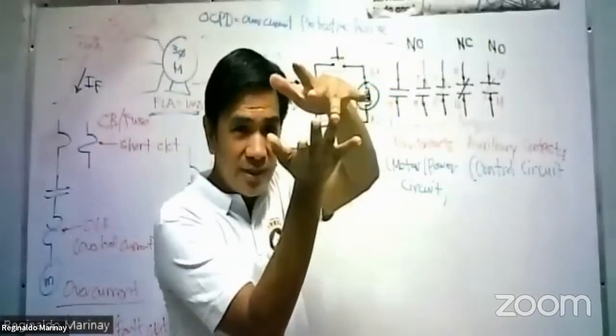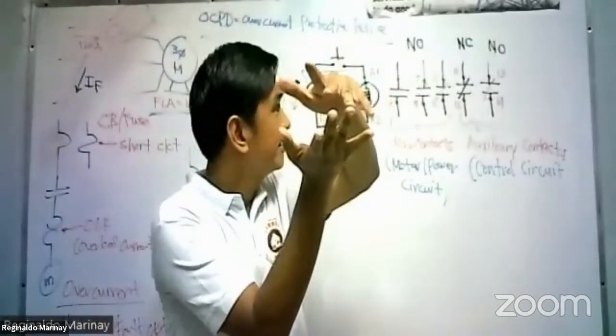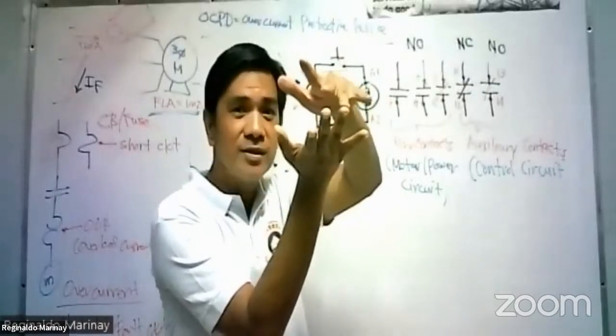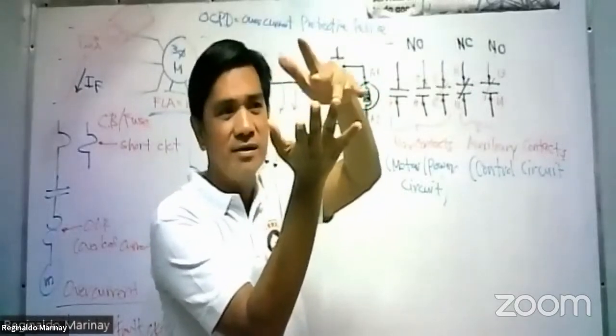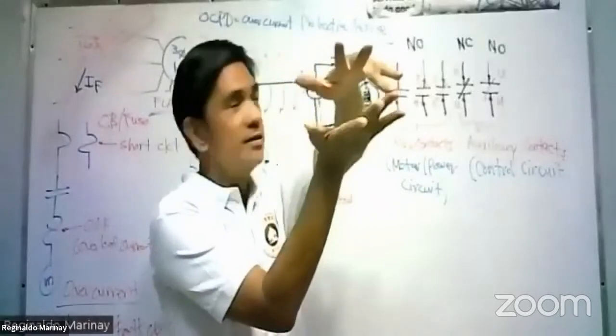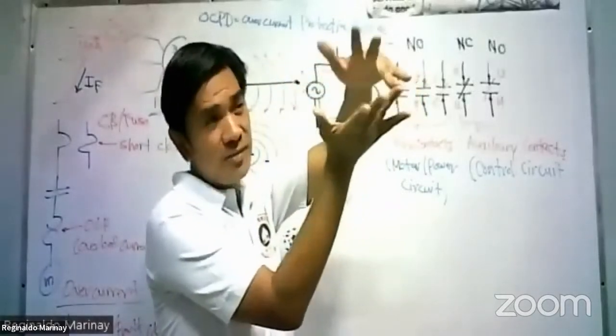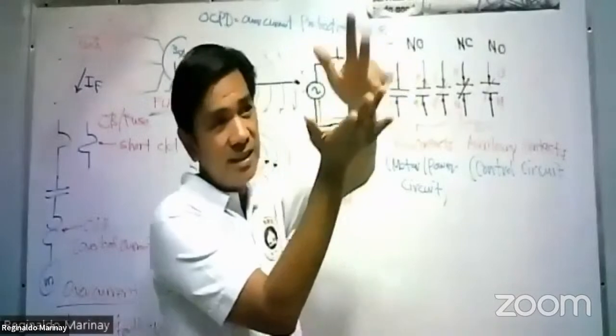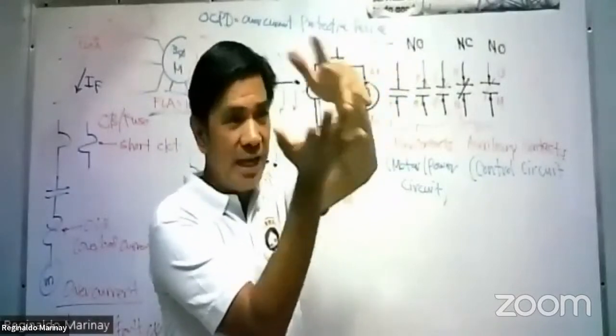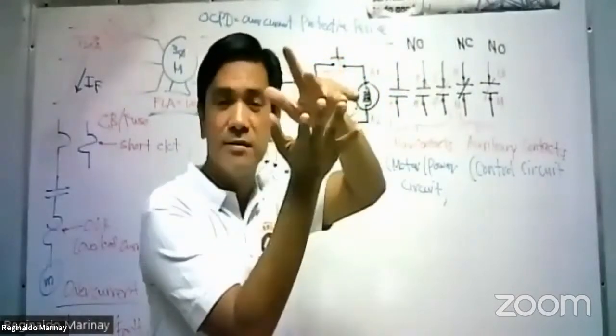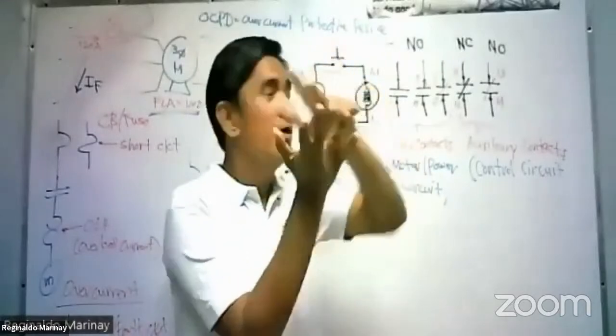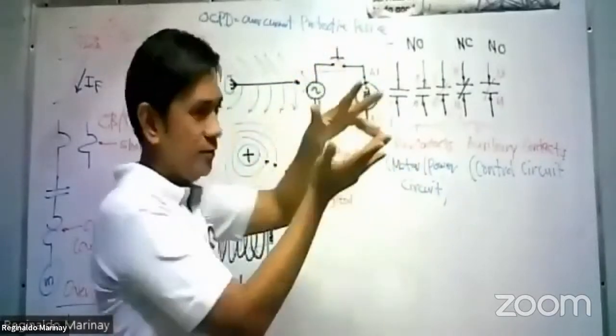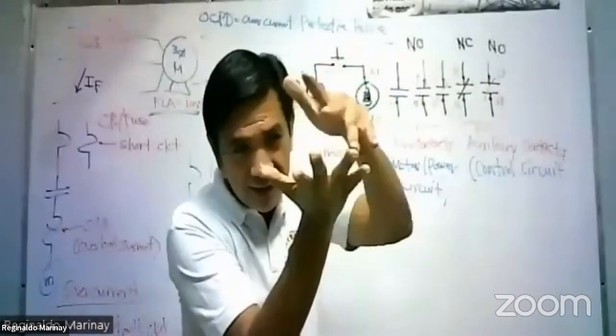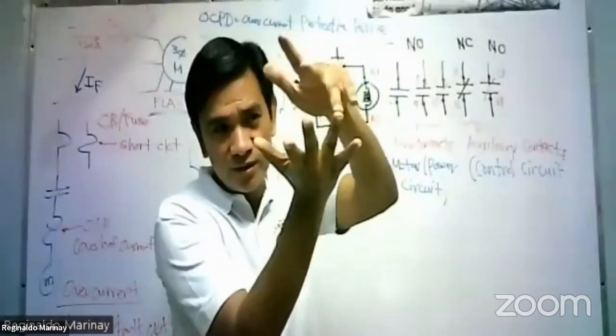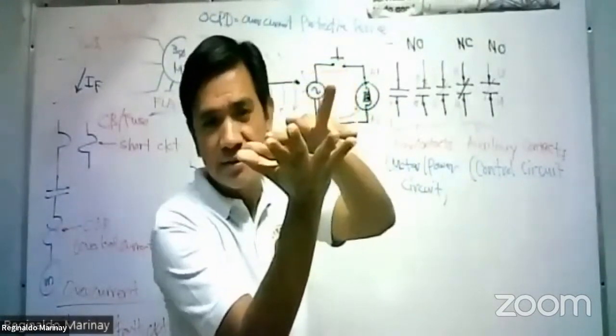And then, what is this? This is 13, and this is 14, which is normally open. 1, 2, 3, 4, 5, 6 are normally open. You see, this is open, and this is closed. That is 11 and 12. And this is 13 and 14, and this is normally open. Once you energize this circuit, all the normally open contacts, you will see inside the magnetic contactor, this will happen.